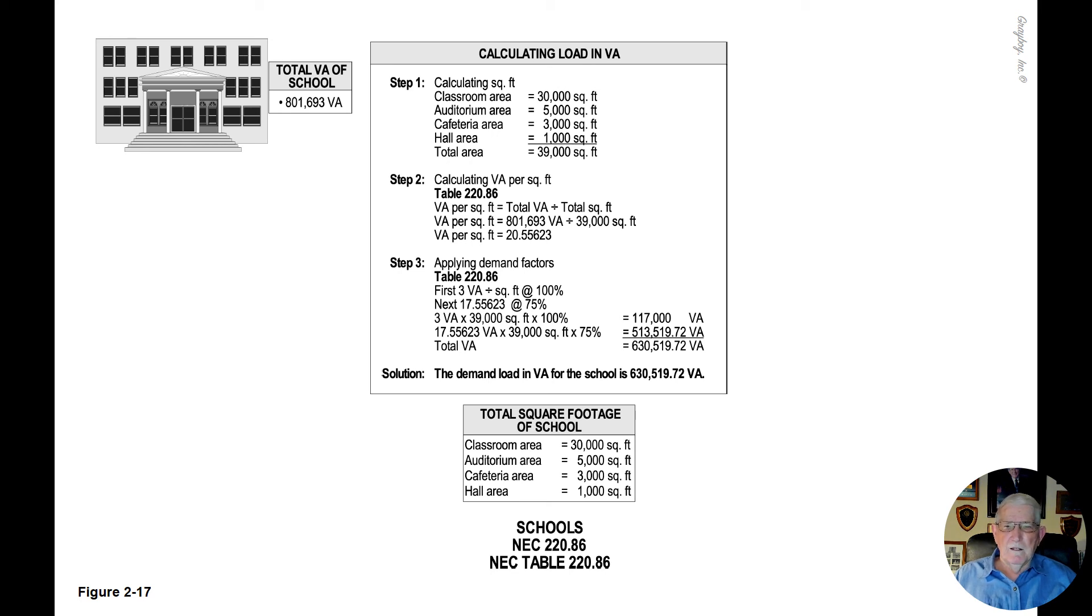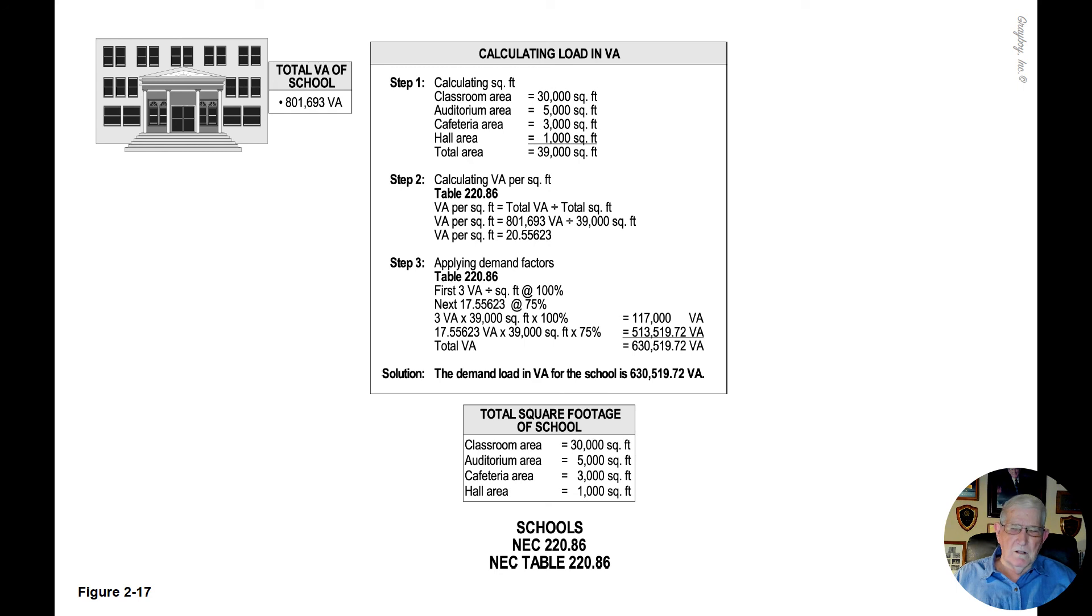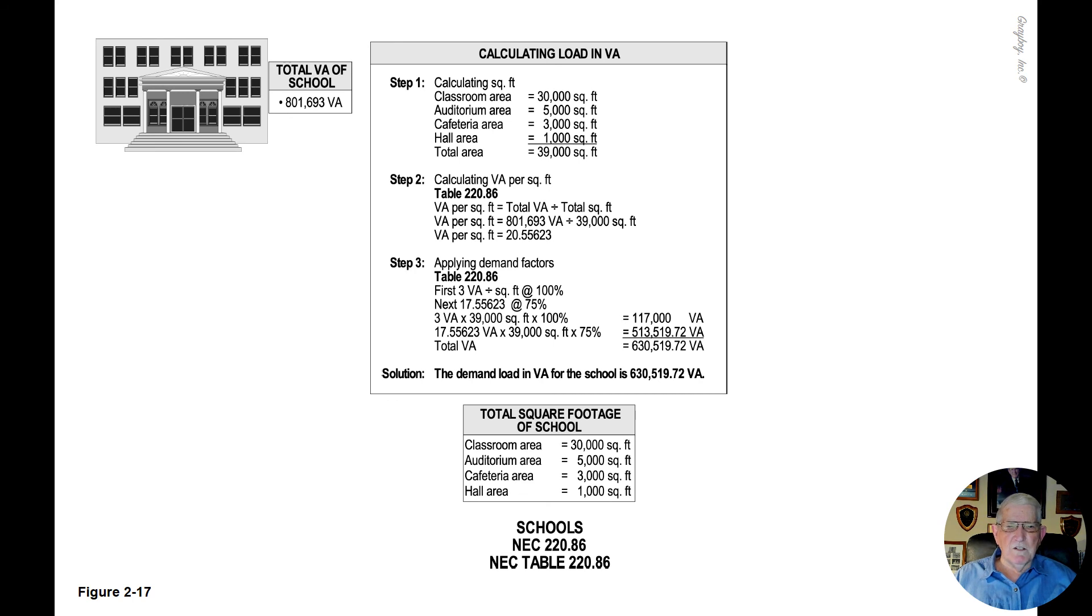When we take 17.55623 times the 39,000 square foot times 75%, we come up with a total of 513,519.72 VA.